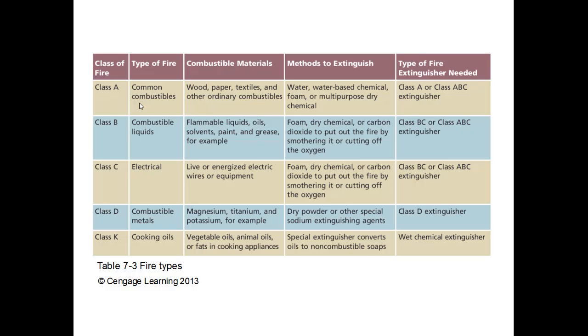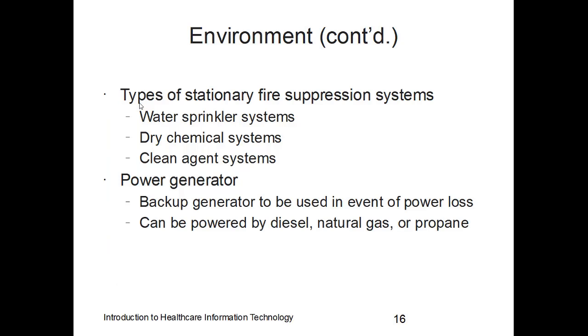Class C fire is an electrical fire involving live or energized electrical wires or equipment. Class D involves combustible metals such as magnesium, potassium, and titanium. Class K involves cooking oils such as vegetable oils, animal oils, or fats in cooking appliances. For fire suppression systems, you can have a standard water sprinkler system, a dry chemical system, or a clean agent system.